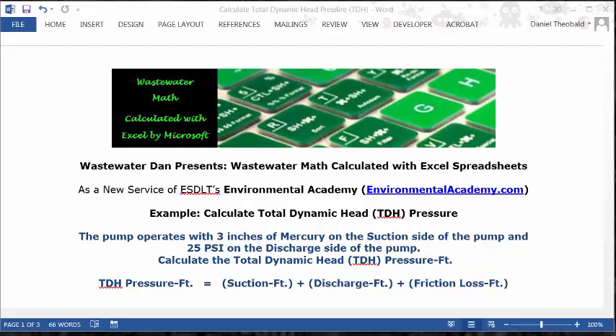The solution for today's problem uses the formula that calculates TDH, which equals the suction pressure in feet plus the discharge pressure in feet plus the friction loss pressure in feet.